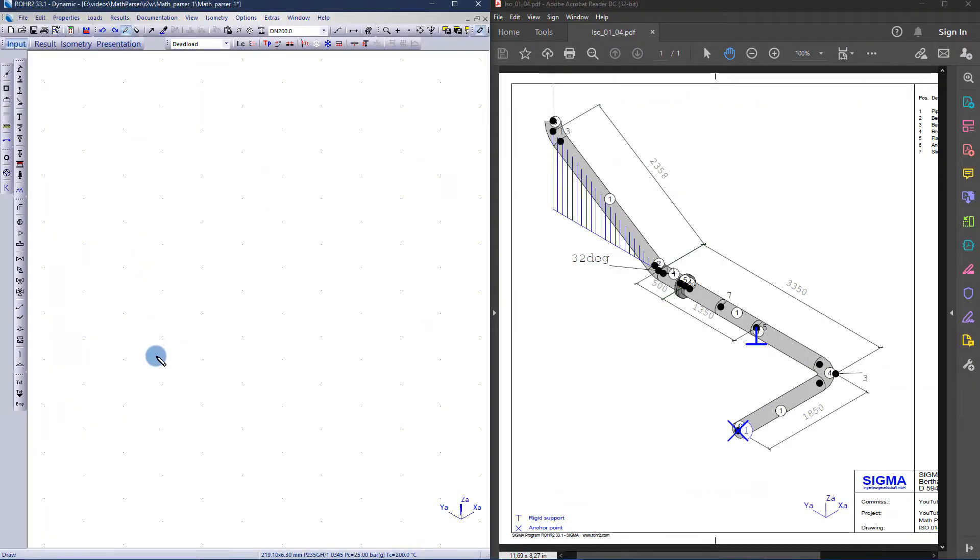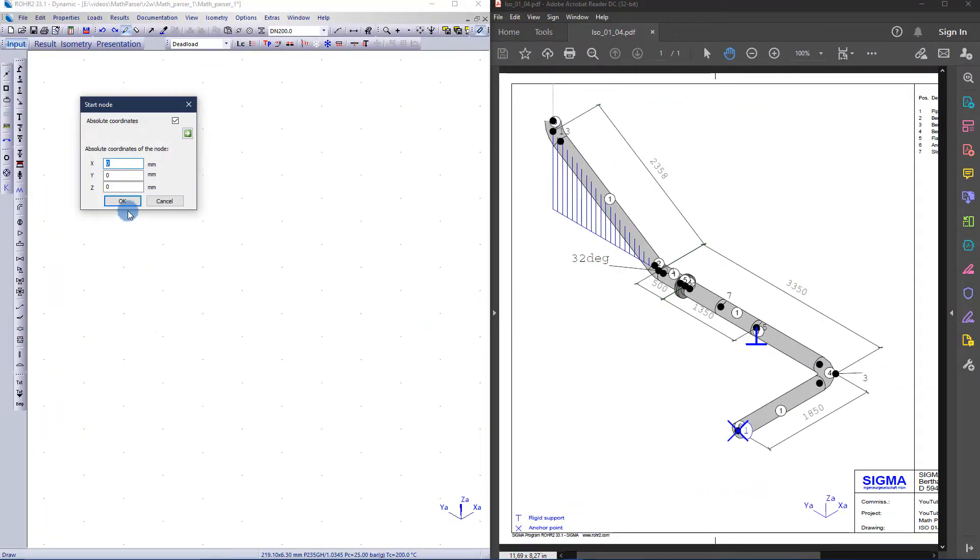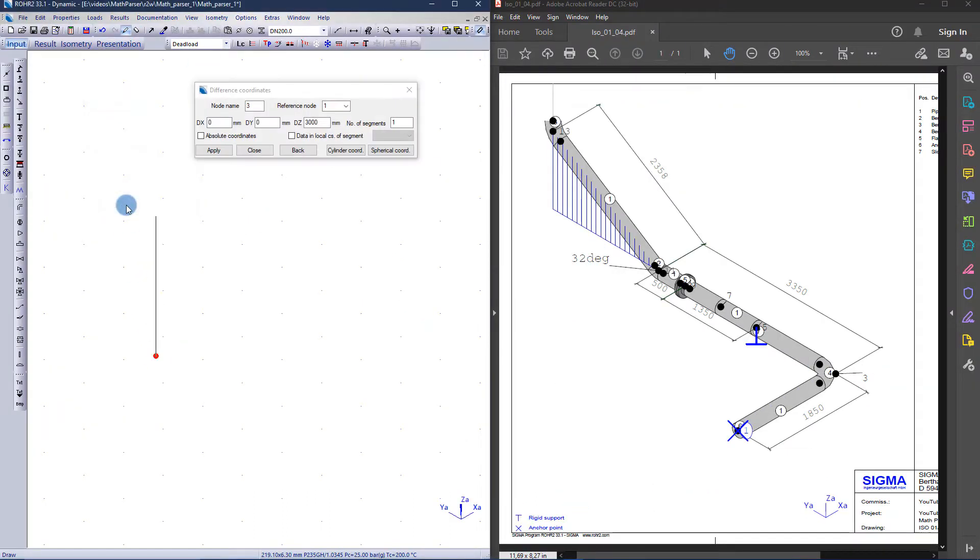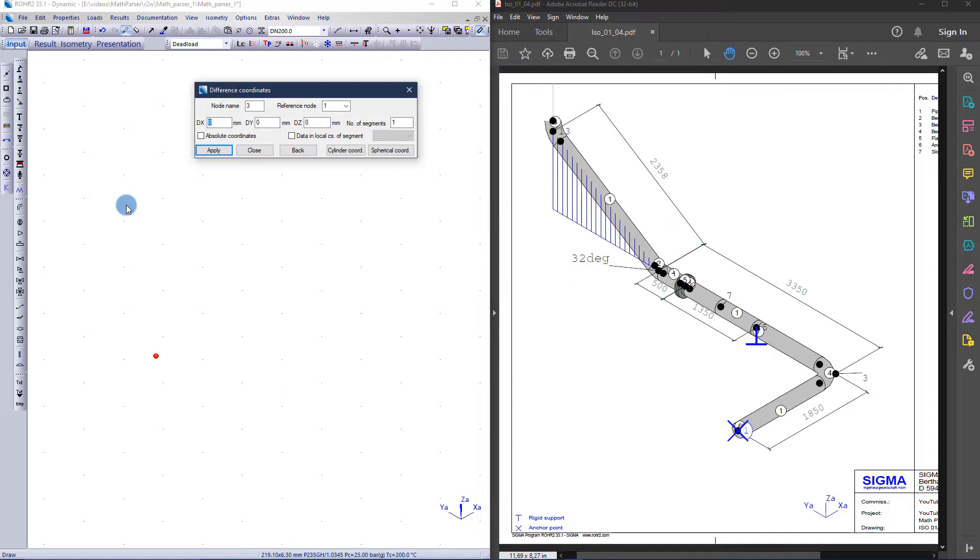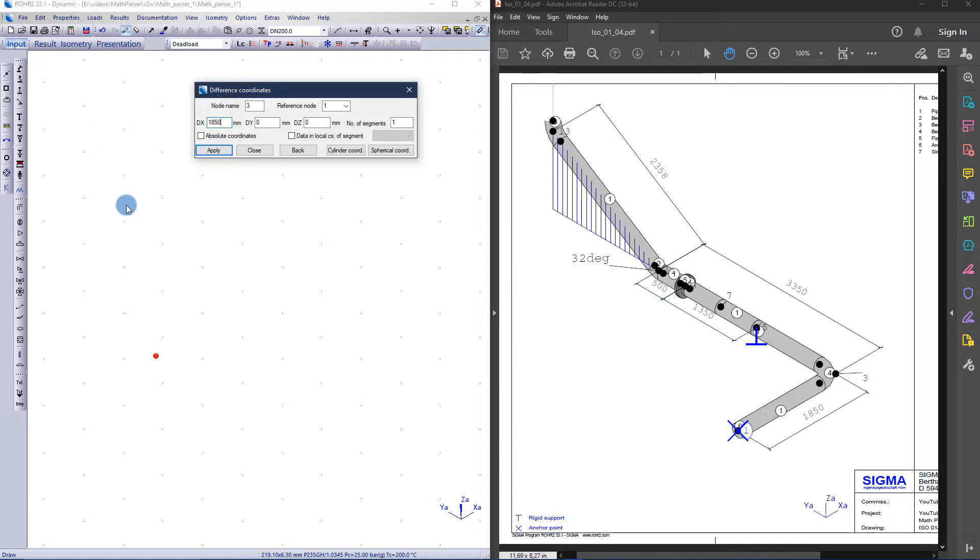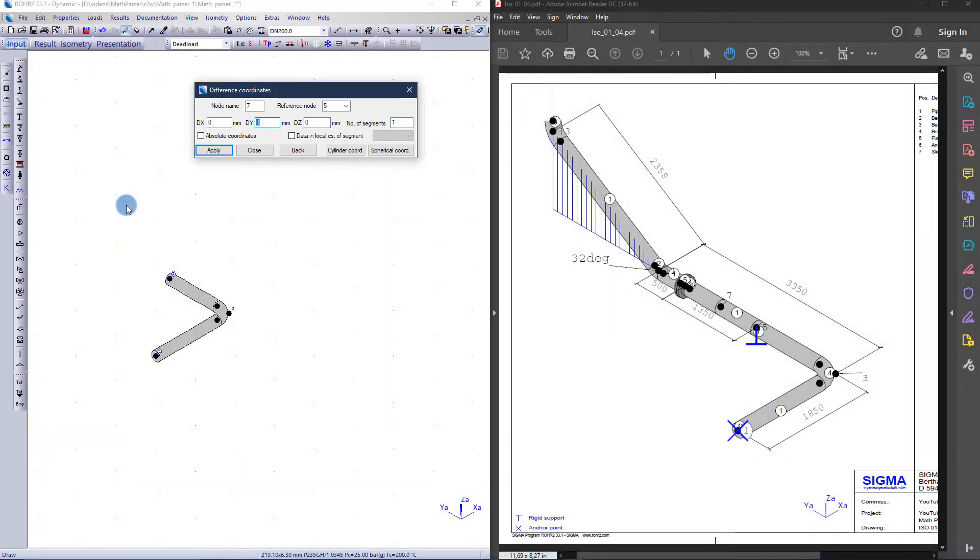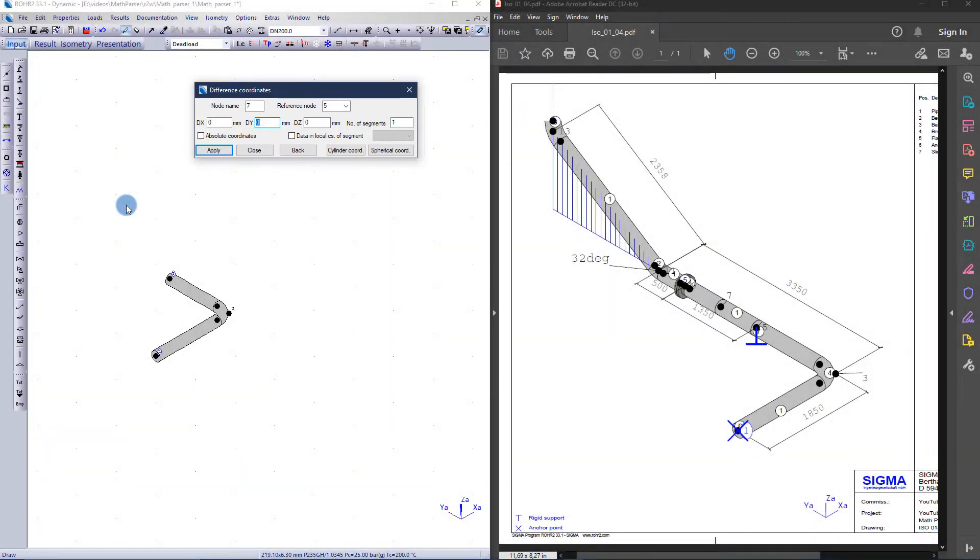The isometric drawing at hand should be modeled in ROHR2. In this case I would like to map the intermediate nodes for the sliding support and the flange connection. Therefore the distance from the bend to the flange connection and to the sliding support must be subtracted from the total dimension. This can be done directly in the input field, thanks to the math parser.